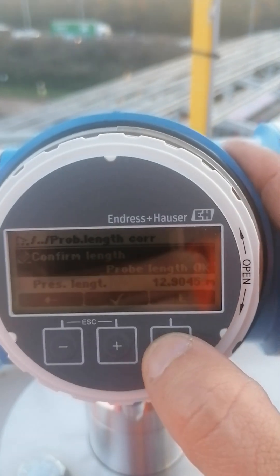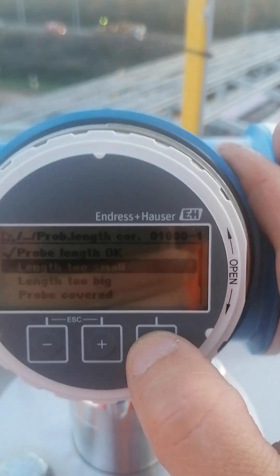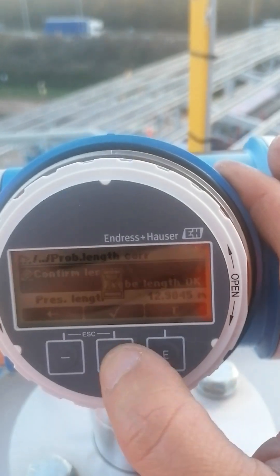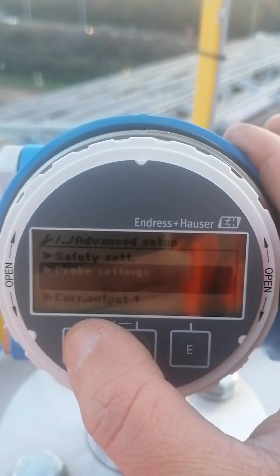It's reading 12.9. I set it too small just to make sure — it's still reading 12.9, so the probe length is confirmed. I press OK and validate. The length of the probe is now set to 12.9 meters.